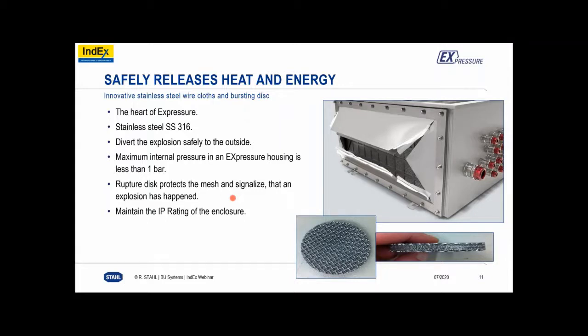And the ruptured disc, what you see on the picture, protects the mesh and signals if an explosion has happened. The external surface of the ExPressure relief or the explosion vent maintains the IP rating of the enclosure. So it's also a protection of the mesh itself, also from dirt and dust, for example. In the event of a blowout through the ruptured disc, or in case of a damaged or deformed ruptured disc, they have to be replaced by identical new ruptured discs, which can be ordered as an accessory from R.Stahl.